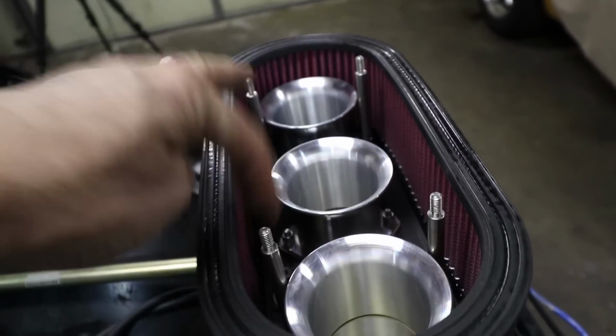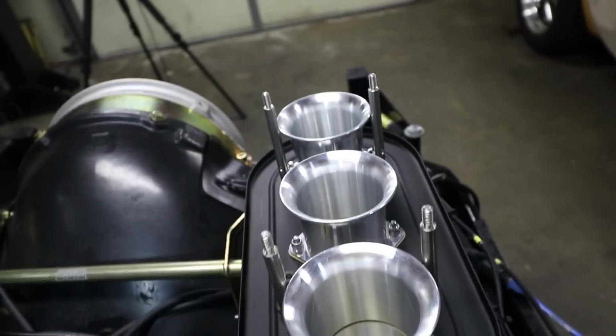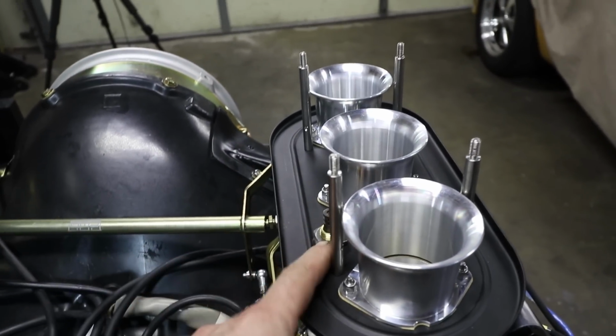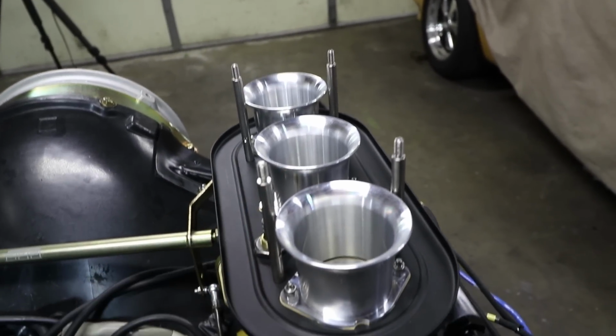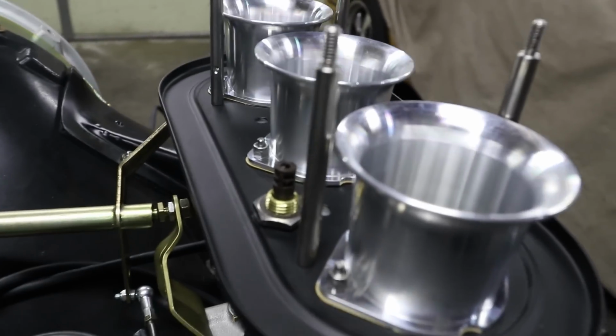So it's getting filtered air, measuring what is about to go into the engine. This is important for fuel density calculations, air density calculations. So let's go ahead and calibrate this. Right now it's showing on the computer an intake inlet air temperature of 25.2 degrees C. That seems about right. Right now my temperature outside is about 23 C.